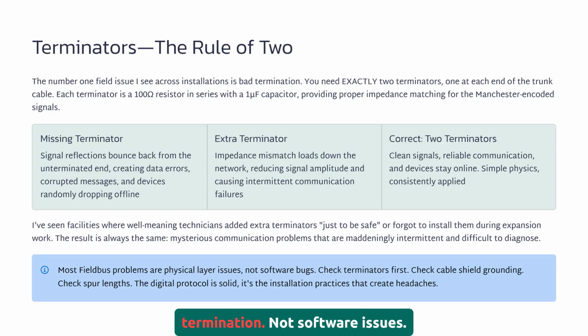Bad termination. Not software issues. Not configuration issues. Physical layer problems. Here's the rule of 2. You need exactly 2 terminators, 1 at each end of your bus. Your trunk line has a starting point and an ending point. Each one gets a 100 ohm resistor in series with a 1 microfarad capacitor. That's the terminator. It terminates the transmission line properly, so you don't get reflections, noise, or signal degradation.